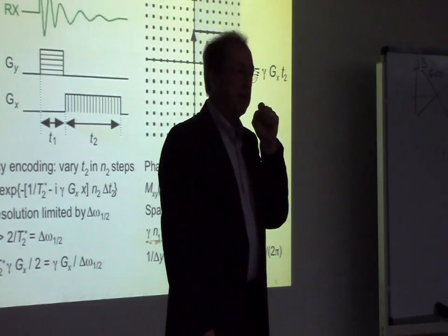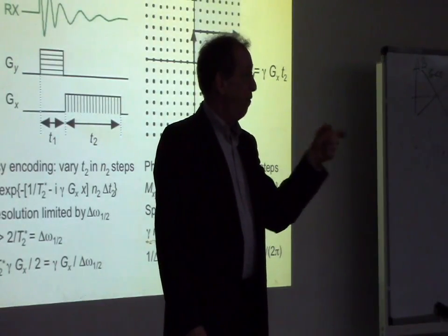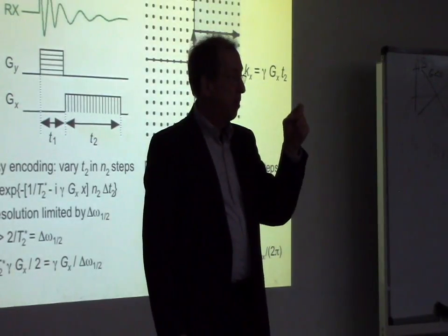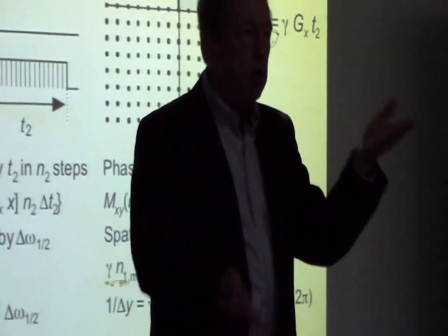Pretty complicated stuff, huh? Very different from spectroscopy. So it's the NMR phase, that little precession angle, which you can split up into different contributions of a spin being at rest, of a spin moving, or of a spin being accelerated. And that you can measure with the different moments of the gradient modulation function. And the gradient modulation function is how you turn the gradients on and off and what values you give them.